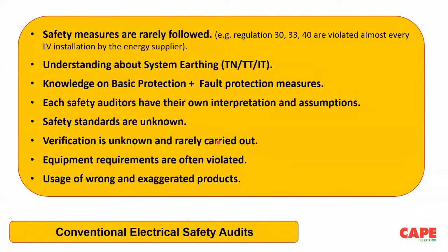Safety standards are unknown, and verification is unknown and rarely carried out. As I said, please note that I am not using the word safety audit, I am using the word verification. Audits are made, but the result of the audit is a question. Verification is rarely carried out. Equipment requirements are often violated. Wrong and exaggerated products are used. As I said, the exaggerated products are things like digital earthing and chemical earthing. Nowadays, most of these chemical earthing companies become electrical safety auditors. So when a chemical earthing company becomes an electrical safety auditor, the result is that he will recommend 25 more earth pits. The client buys them and installs them. This is actually not correct.